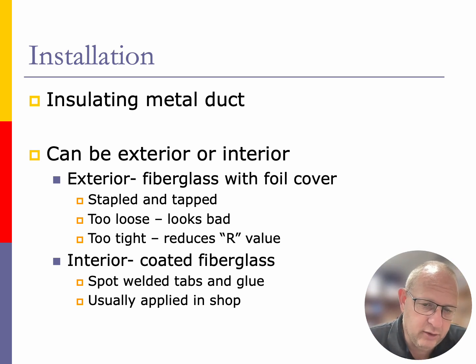Another reason to put exterior insulation on your ductwork is that the glue and the tabs can fall off on the inside of the ductwork and cause an air restriction. It's hard to see because it's interior, but it's only diagnosed because you have bad pressures on your low side system or your furnace is kicking off on high temperature within that system itself. Interior insulation is usually applied in the shop as they're making that ductwork up.